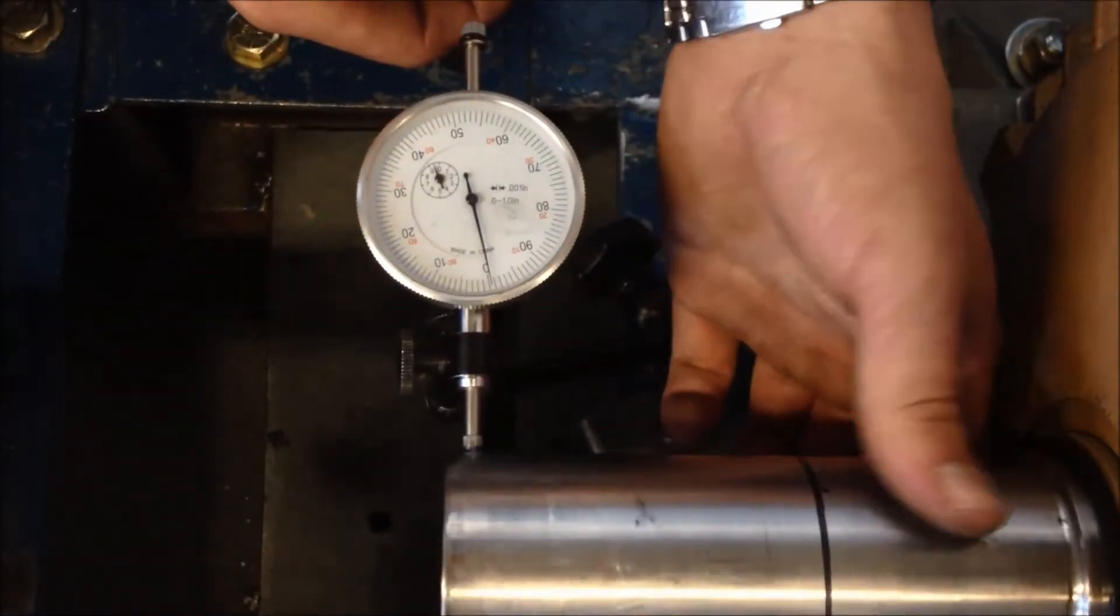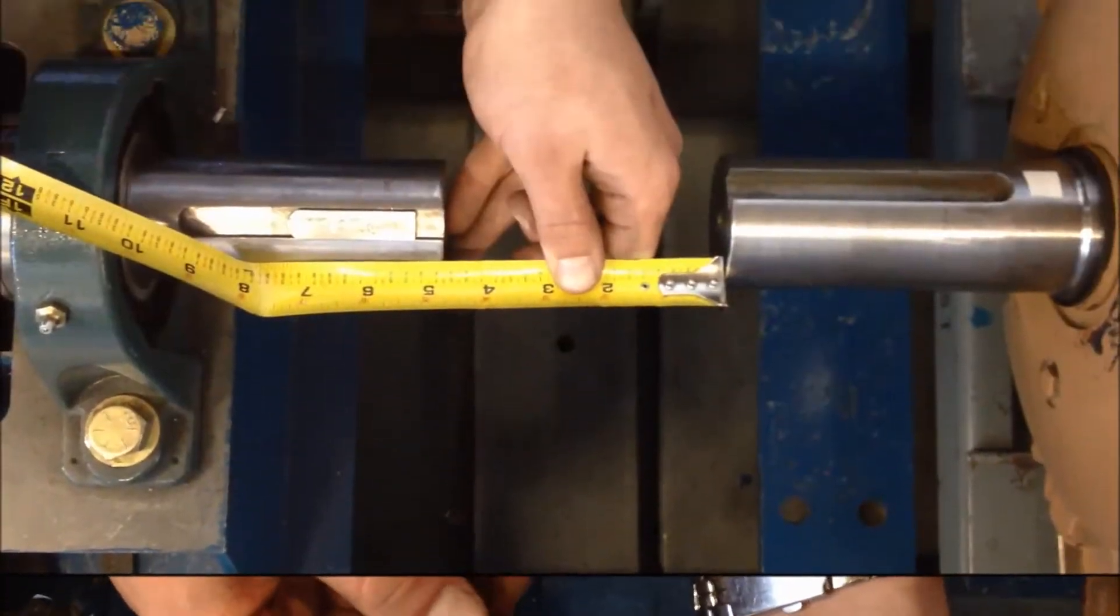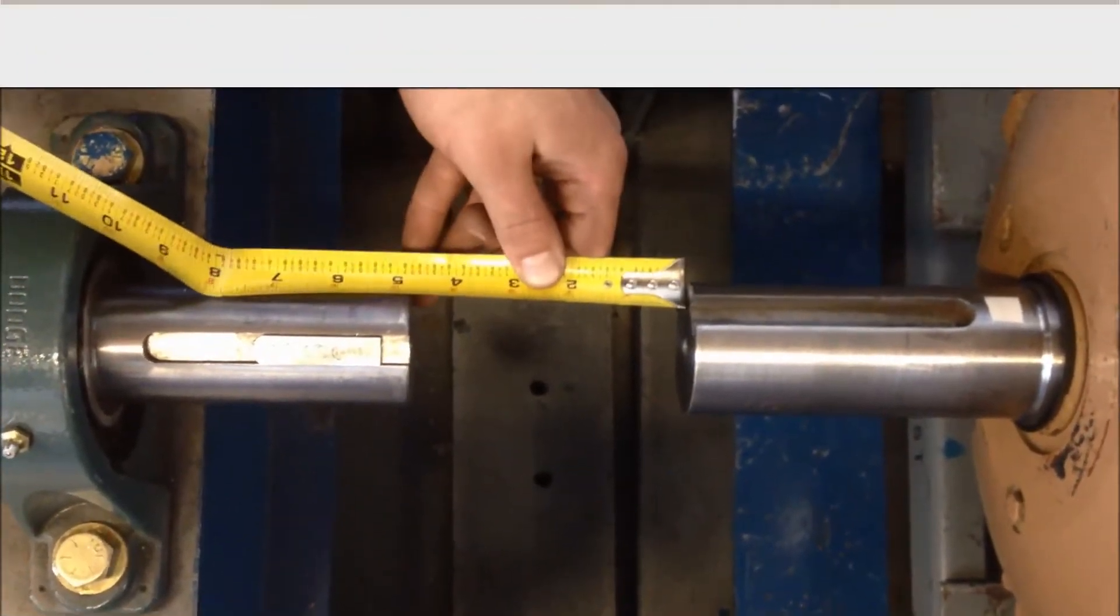Measure the distance between shaft ends. To install the coupling without moving the motor, 4.5 to 5 inches is required when using a 1 inch hub spacer.